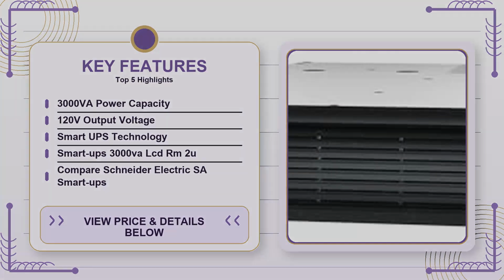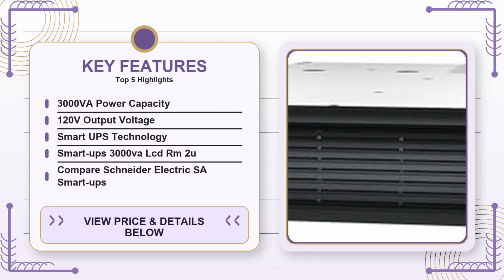Now, who should probably skip this model? If you live in a home office with a single desktop and a monitor, you're probably overkill. The 3000VA rating translates to a higher price point, and you would never tap into its full capacity. In that scenario, a 600VA to 1000VA 1U UPS would provide enough backup for a typical PC setup at a fraction of the cost. Likewise, if you're managing a large enterprise data center with hundreds of kilowatts of load, you'll need a Tier 1, high-capacity UPS that can handle megawatts of demand. The Smart UPS 3000VA simply cannot scale to that level.